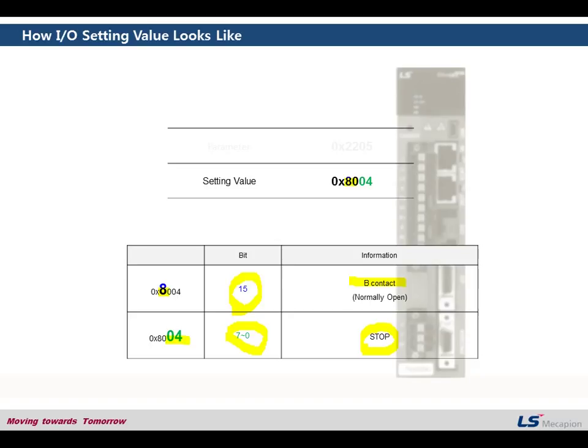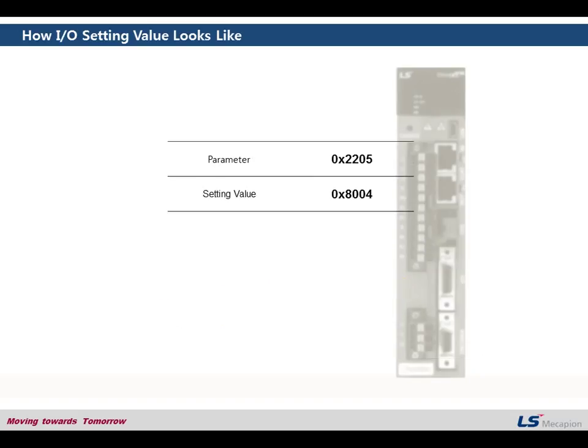As we have talked in previous page, there are 15 functions and you can choose 8 functions for input and this stop function is one of them. So now you know what they mean. It's very simple. Assign the stop function as an input signal 6 with a B contact which is normally closed.